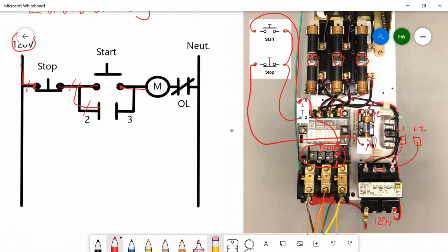So now we've got the start connected to the coil of the motor starter, represented here by this circle and this M, meaning M for motor starter contactor. And we've also got the jumper over to the other side of our normally open contact that we're using as a latching for the contactor, because these are momentary switches. Whenever we press down on the stop or the start, it reverts back to its original condition. In this particular case, the stop button has a normally closed set of contacts, and the start has a set of normally open contacts. All right, so now we've completed that side of the ladder logic.